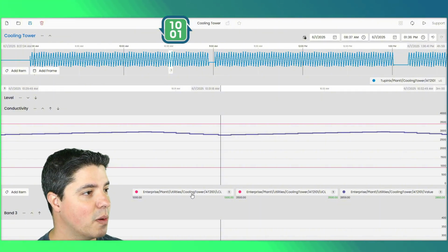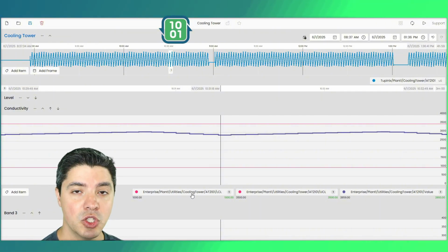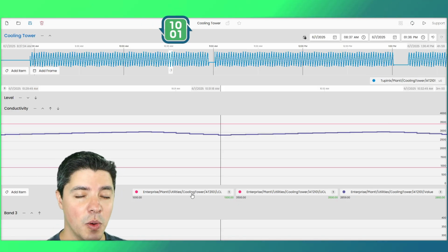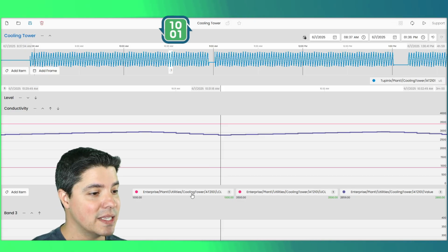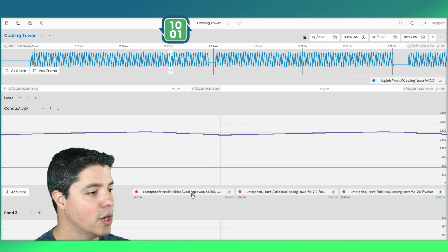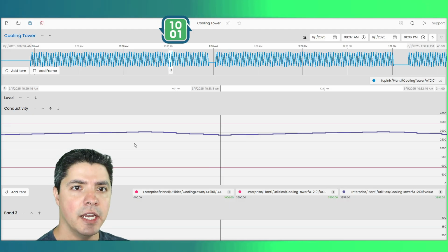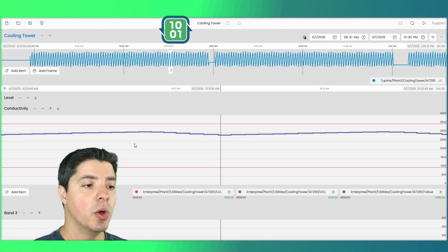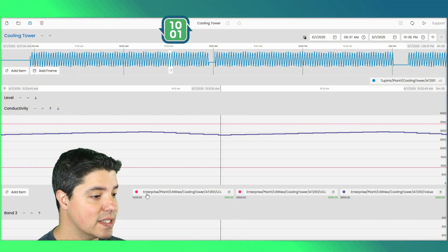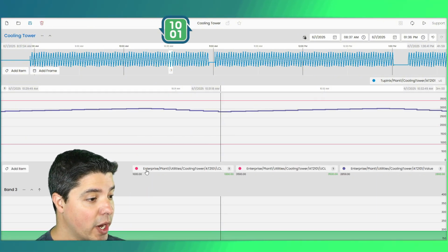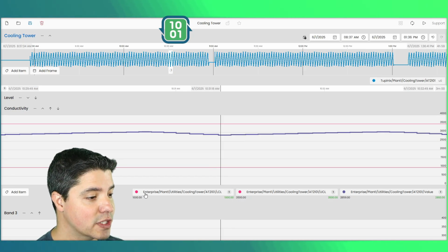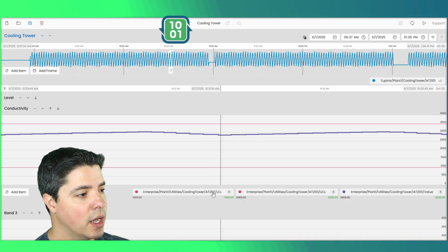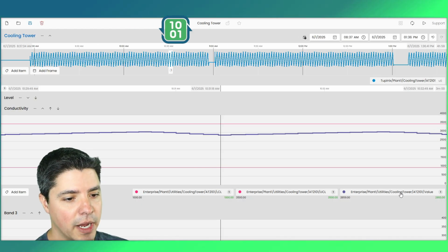Where is this coming from? This one is Sparkplug B. So all we did here was collect a bunch of data from sensors, not even going to the PLC. We bypassed that through the IIoT port. And then we got this data in Ignition. We normalize, we contextualize it in there. So now we format it in there. So this is being sent straight from Ignition to the Timebase module. It goes to enterprise, plant 1, utilities, cooling tower, all the way here, my upper and my lower limits.